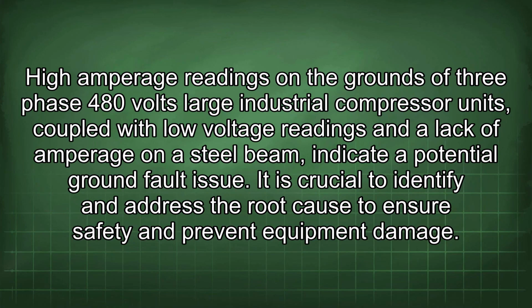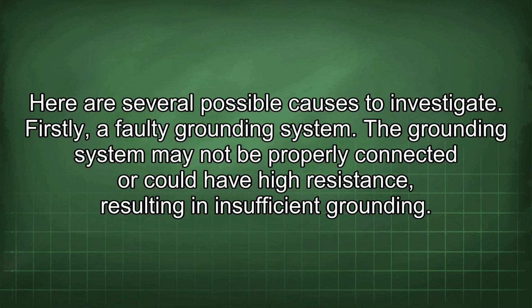High amperage readings on the grounds of 3-phase 480 volts large industrial compressor units, coupled with low voltage readings and a lack of amperage on a steel beam, indicate a potential ground fault issue. It is crucial to identify and address the root cause to ensure safety and prevent equipment damage. Here are several possible causes to investigate.